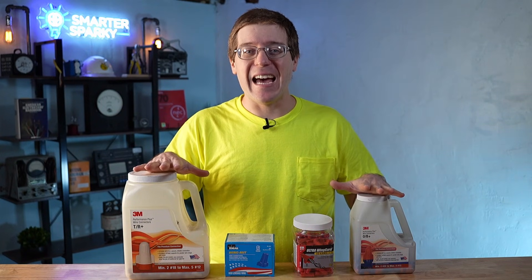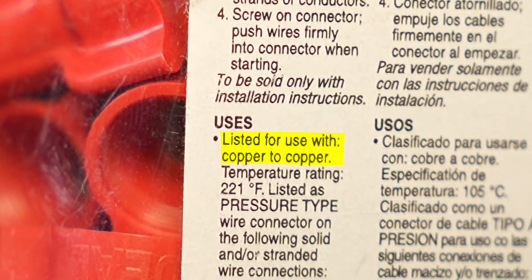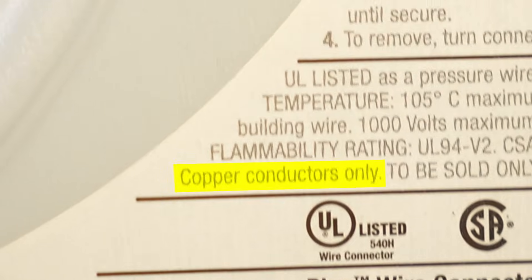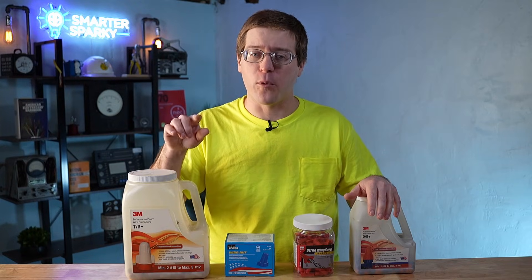Another consideration is that most standard wire nuts are only listed for use with copper conductors, not aluminum. If you are connecting to aluminum wires, make sure your wire nut connector is specifically listed for that use.